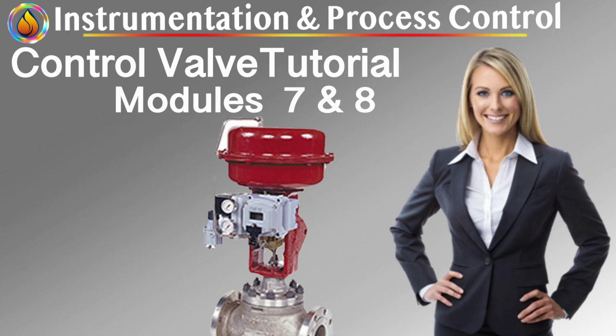Static performance. Static performance describes how a valve behaves once it has settled, independent of time. These characteristics define the minimum controllable change a loop can achieve. Deadband. Deadband is the range of input signal change that produces no valve movement. Engineering sources: packing friction, seal drag, stem misalignment, mechanical clearances, poor positioner tuning. Control impact: small controller corrections are ignored, offset persists even with integral action, and the loop exhibits limit cycling around set point. Deadband is especially damaging in temperature control, composition control, and tight regulatory loops. A valve with excessive deadband behaves like a controller with a blind spot.